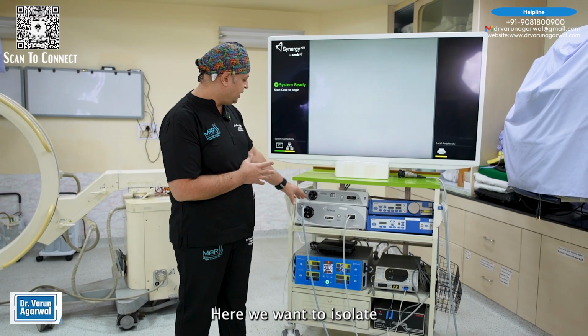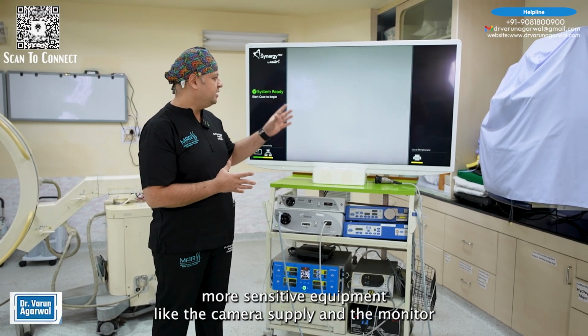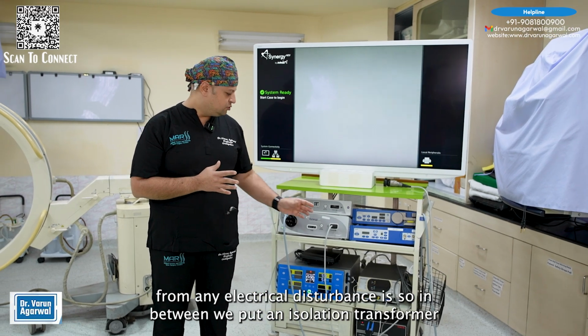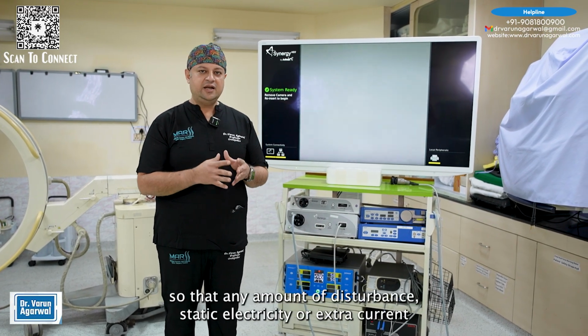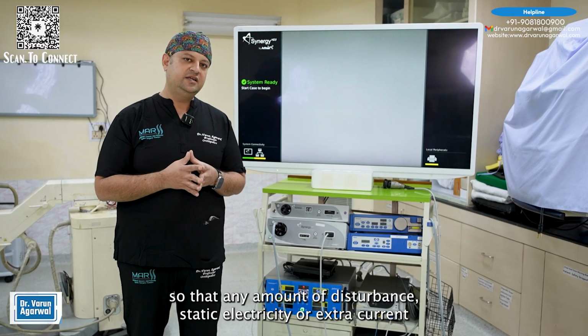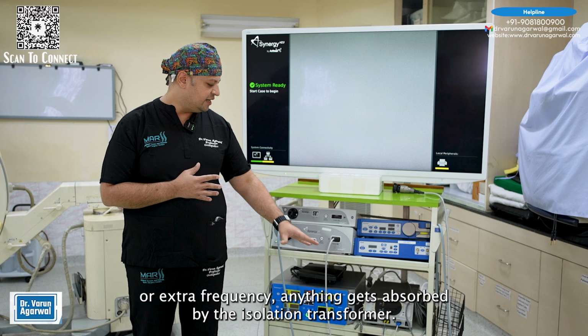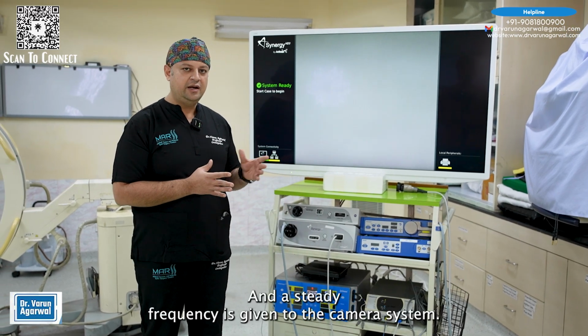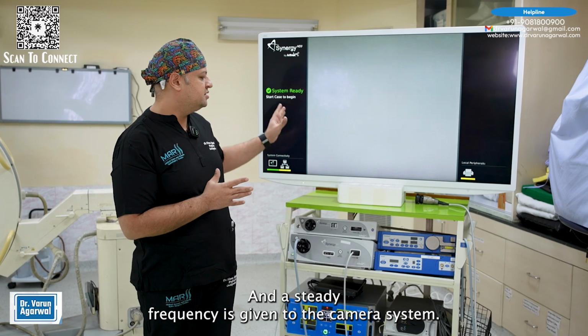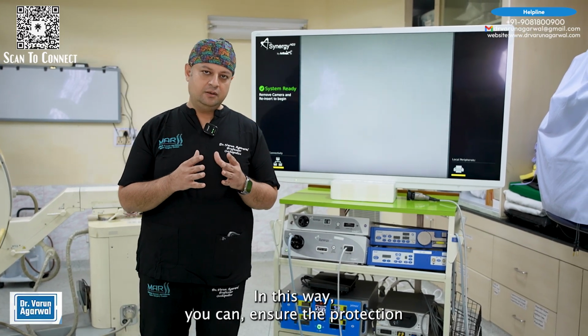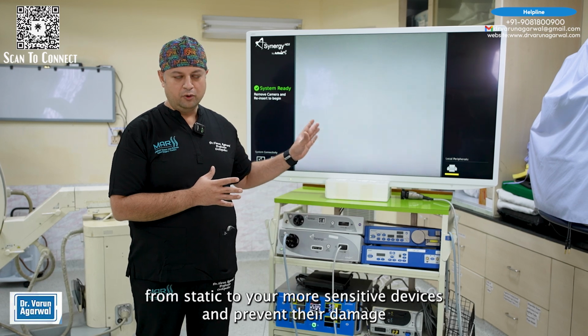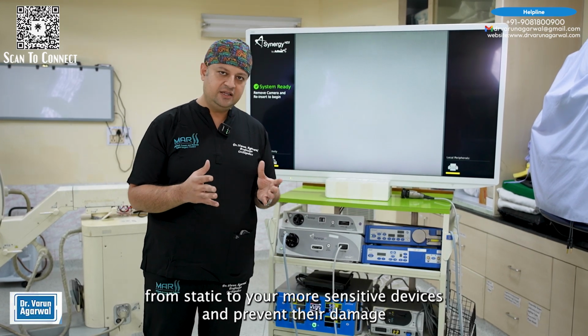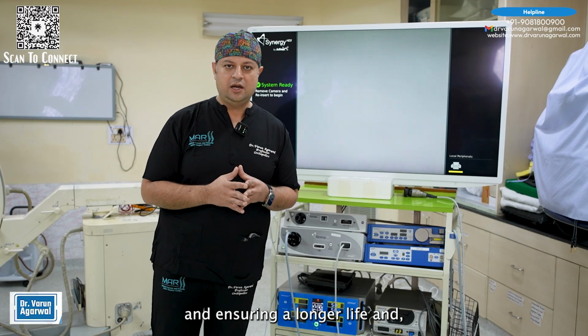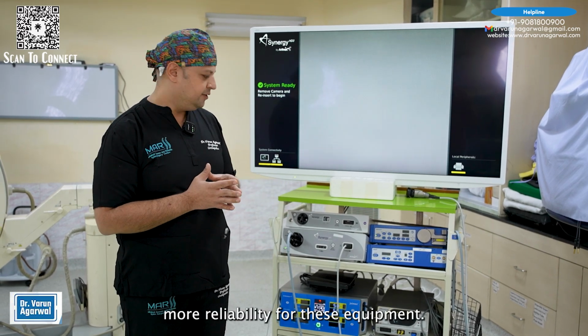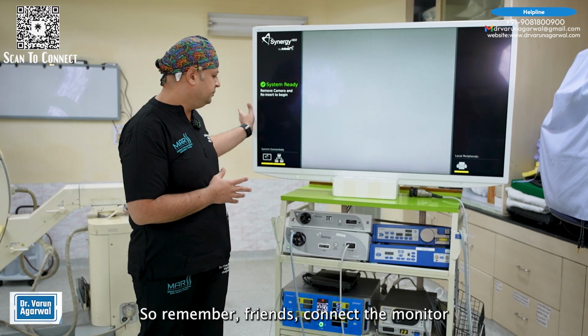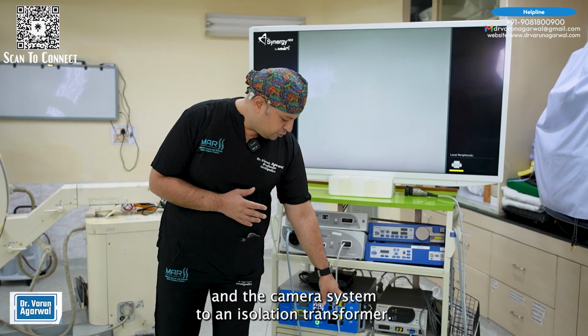Here we want to isolate our more sensitive equipment like the camera supply and the monitor from any electrical disturbances. So in between we put an isolation transformer so that any amount of disturbance, static electricity, extra current or extra frequency gets absorbed by the isolation transformer, and a steady frequency is given to the camera system. In this way you can ensure protection from static for your more sensitive devices and prevent their damage, ensuring a longer life and more reliability for this equipment. So remember friends, connect the monitor and the camera system to an isolation transformer.